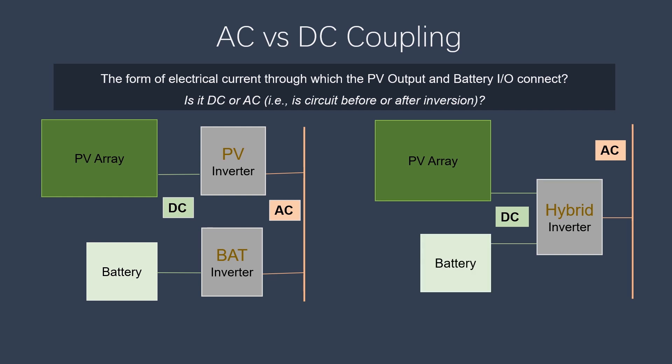On the right side, we have the same PV array but connected to a hybrid inverter, which has a DC bus bar. Therefore, there is no conversion to AC between the PV array and the battery. The left side is an example of AC coupling; the right side is an example of DC coupling.